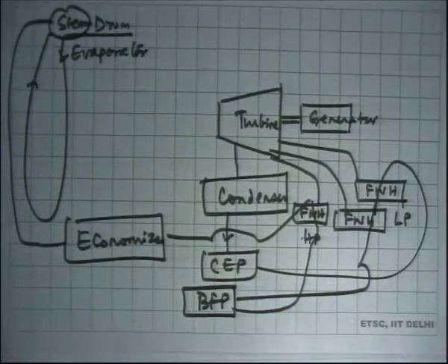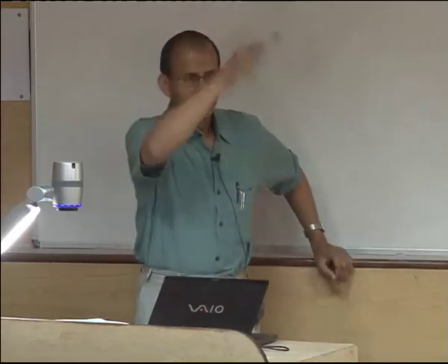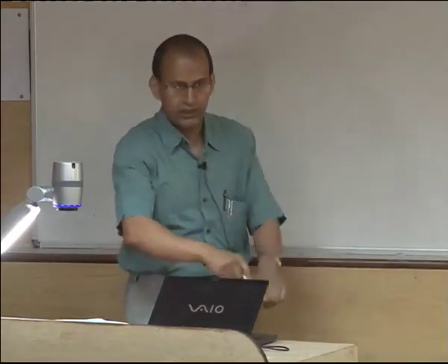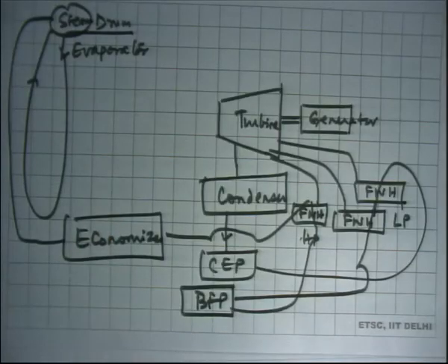Okay. So, the pipes taking the water downwards are outside the boiler, and then the entire wall of the boiler is lined with pipes that take the water back up to the boiler drum. So, you have loops that come from the boiler drum down to the header at the bottom and then climb through the boiler, get evaporated and go up back to the steam drum.